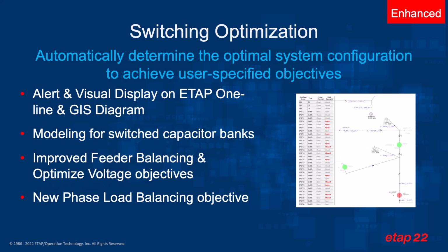Switching optimization is particularly used to determine the optimal system configuration to achieve certain user-specified objectives, such as minimizing real and reactive power losses or minimizing the amount of unbalance in a particular system. Switching optimization in ETAP 22 has been enhanced to include the alert and visual display on the ETAP one-line diagram and the GIS diagram as well. We can now include the modeling for switched capacitor banks in the power flow simulation and improved the feeder balancing and optimizing voltage objectives as well to be more precise and accurate. We have also included a new phase load balancing objective as part of the switching optimization module.